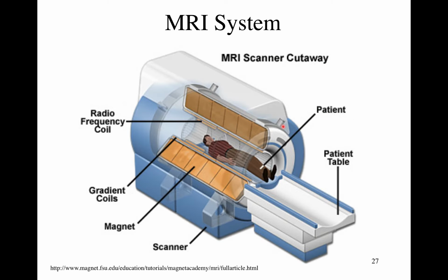This is what a new, fangled NMR system looks like. It has a very large cylindrical tube, and inside, the primary thing inside that cylindrical tube that makes this work are coils that have superconducting current running in them. And the current is so high that it produces a very large magnetic field, like 50,000 times the Earth's field, things like that.